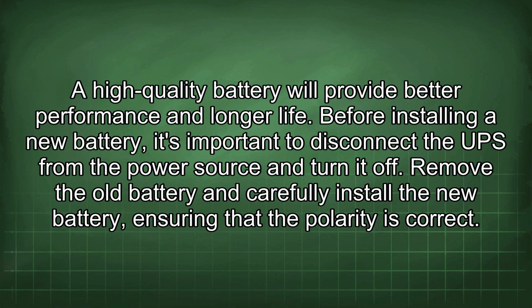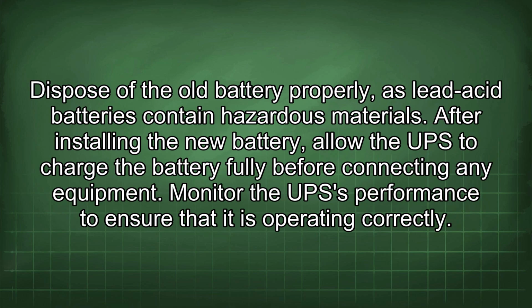Before installing a new battery, it's important to disconnect the UPS from the power source and turn it off. Remove the old battery and carefully install the new battery, ensuring that the polarity is correct. Dispose of the old battery properly, as lead-acid batteries contain hazardous materials. After installing the new battery, allow the UPS to charge the battery fully before connecting any equipment. Monitor the UPS performance to ensure that it is operating correctly.